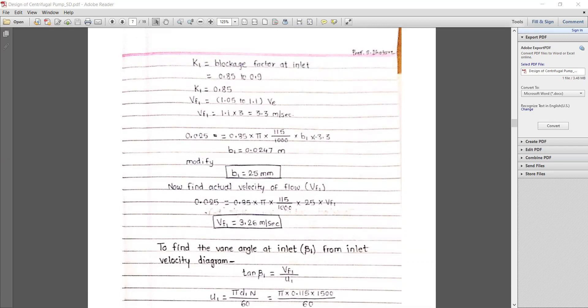Substituting: 0.025 = 0.85 × π × (115/1000) × b1 × 3.3, giving b1 = 0.0247 m = 24.7 mm, which we round to the standard dimension of 25 mm. Recalculating with this standard width, the actual flow velocity vf1 = 3.26 m/s.